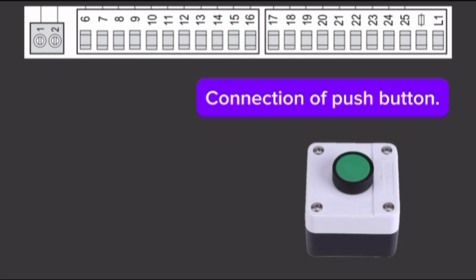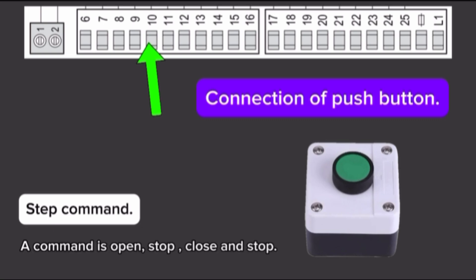Connection of push button. In the control board terminal 10. Step command. A command is open, stop, close and stop. Connect to push button terminal 10 with common 6.